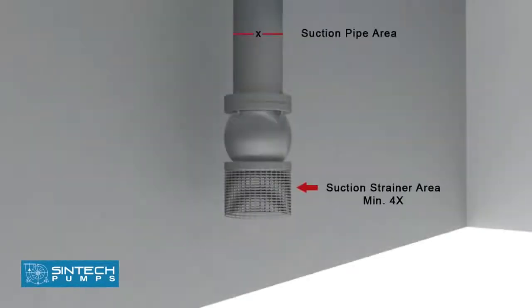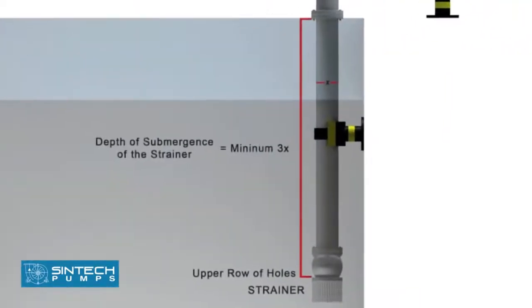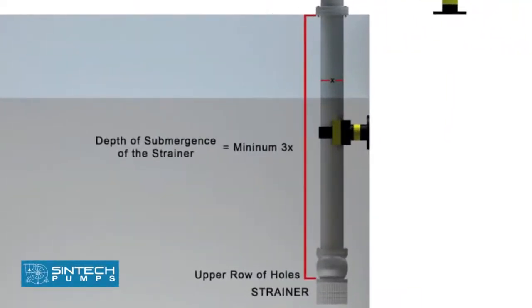The suction strainer must be at least 4 times the suction pipe area and the mesh size should screen out solid particles that could clog the impeller. The minimum depth of submergence of the strainer should be at least 3 times the pipe diameter measured from upper row of holes of strainer.